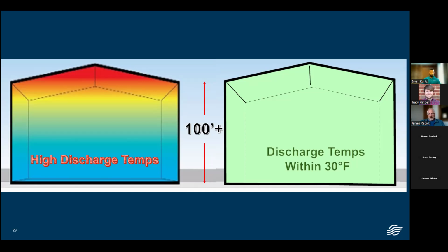100-foot ceiling, large. It was a very, very big aircraft hangar. We had to hold back the stratification or the infiltration with that positive pressure combined with the low discharge temperature. And you just can't get better performance than that, in addition to the air quality that you're bringing to the space by bringing in fresh air.